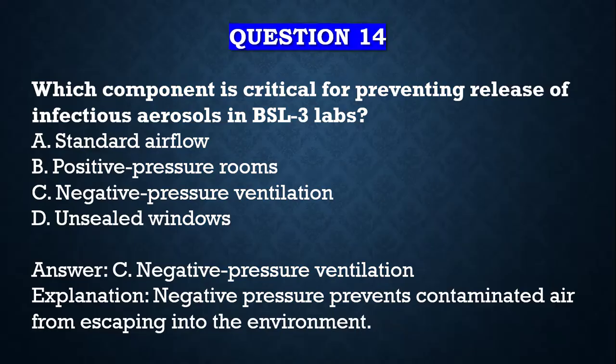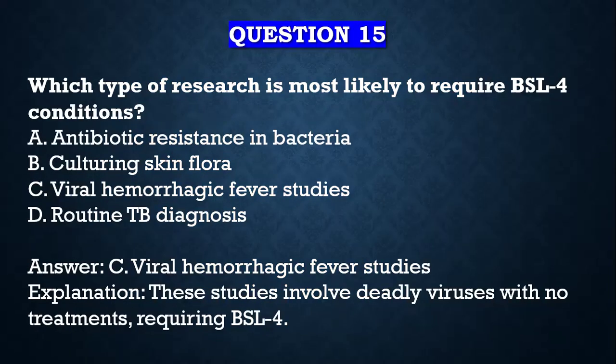Question number fourteen: which component is critical for preventing release of infectious aerosols in BSL3 labs? A) Standard airflow, B) Positive pressure rooms, C) Negative pressure ventilation, D) Unsealed windows. Your answer is C, negative pressure ventilation. Negative pressure prevents contaminated air from escaping into the environment — that's why it's called directional airflow — air flows into the lab but does not flow out.